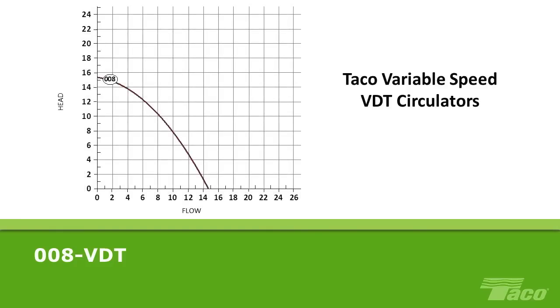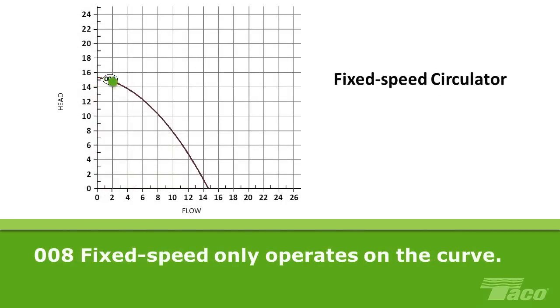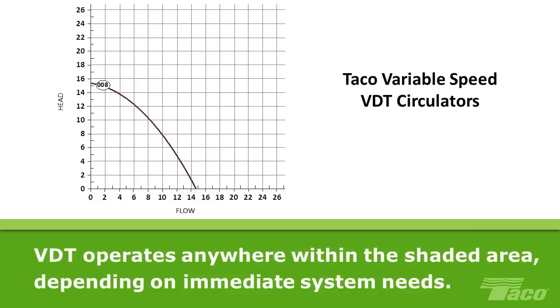That brings us to Taco variable-speed delta-T circulators, which are different from all the pumps we've talked about so far. Here's the curve for the 008 VDT. It looks the same as the curve for any fixed-speed circulator, but you read it very differently. A Taco VDT circulator operates on its own curve, just like every other pump, but it also operates at any other point below the curve depending on the needs of the system. In contrast, the 008 fixed-speed pump can operate only at points along its curve, not above or below it. The pump has no choice but to operate on its curve, regardless of what head and flow the system needs at any given moment. But the VDT variable-speed pump can and does operate anywhere within the shaded area, depending on the specific, immediate flow and pressure needs of the system.